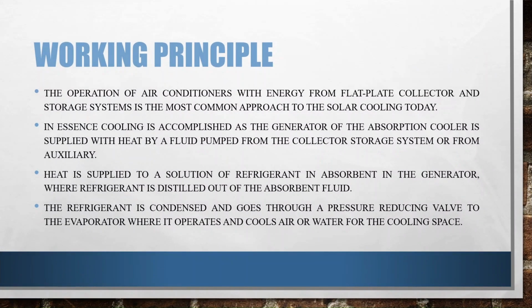So let us see the working principle. The operation of air conditioners with energy from flat plate collector and storage systems is the most common approach to solar cooling today. In a conventional way, we use air conditioners based on the same principle, but here with the energy of flat plate collectors. Cooling is accomplished as the generator of the absorption cooler is supplied with heat by a fluid pump, that is, by the collector storage system or from the auxiliary. Heat is supplied to a solution of refrigerant in absorbent in the generator, where refrigerant is distilled out of the absorbent fluid. The refrigerant is condensed and goes through a pressure reducing valve to the evaporator, where it is operated and it cools air or water from the cooling space.